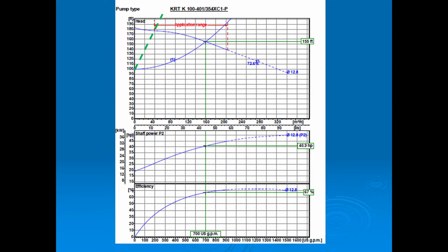What's cavitation, and what does it look like on an impeller? For people who have seen cavitation, I've got pictures on my phone. Well, there you go. Like pitting? It's pitting, absolutely. It depends on how badly you operate to the left of the curve, or closer up to the left where it says shut off, at the very left at 0 GPM at 182 feet on this pump station. The closer you get to that, the worse cavitation becomes. There's air in the water, and it'll start to pit or explode right on the impeller because of the vapor pressure inside that impeller, trying to get the water out of that pump.